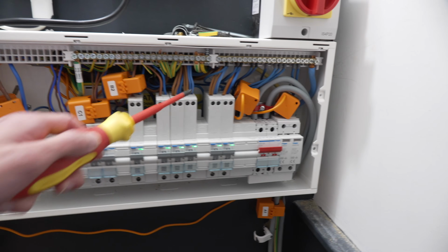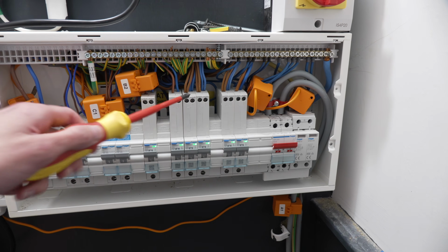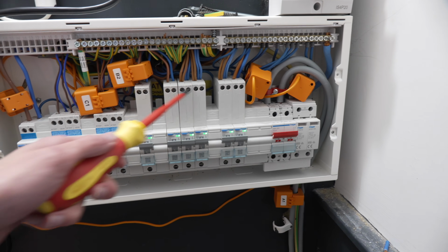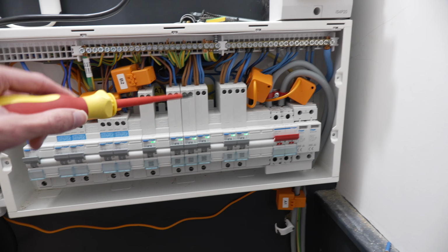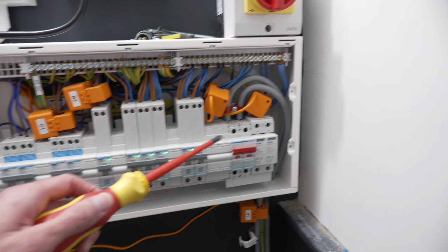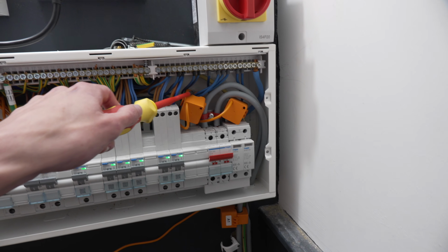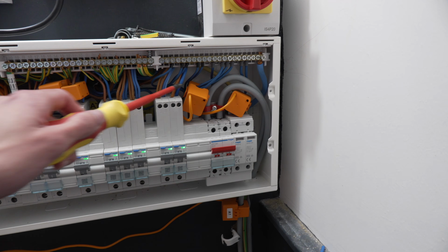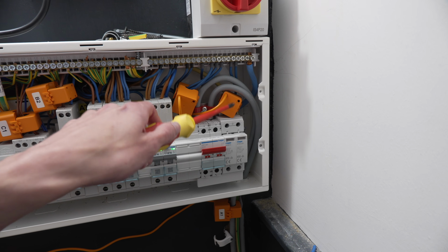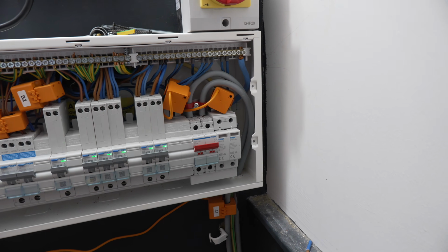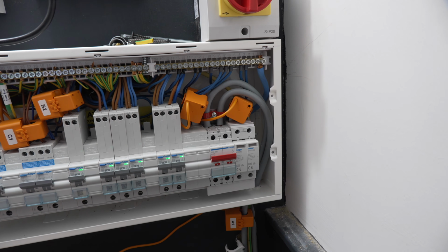And then, as I mentioned before, because these circuits are all so close together, there's not much space, and I want to monitor 3 circuits in one CT for the sockets. Rather than putting the CTs over here, I've put them around the neutral conductors. So we have this CT here that goes on the 3 neutral fly leads for the socket circuits, and this CT here is on the 2 neutral fly leads for the kitchen circuits. And that's all installed absolutely fine.